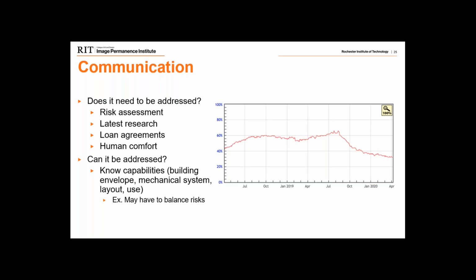An example of this, where our risks might have to be balanced, is shown in the graph of the data on the right, from an institution that saw the relative humidity increasing to 60%, with the trend continuing to increase. This represented a risk that needed to be addressed, and they didn't have complicating loan agreements or human comfort concerns, but they did need to address it from a collections perspective. Unfortunately, due to limitations in the mechanical system, it wasn't possible to increase dehumidification. So what they ended up doing was increasing the temperature to artificially lower that relative humidity.